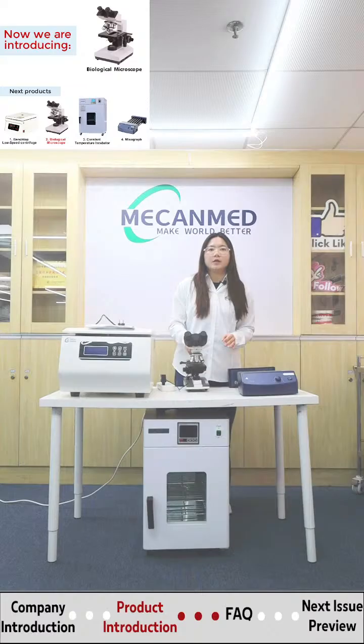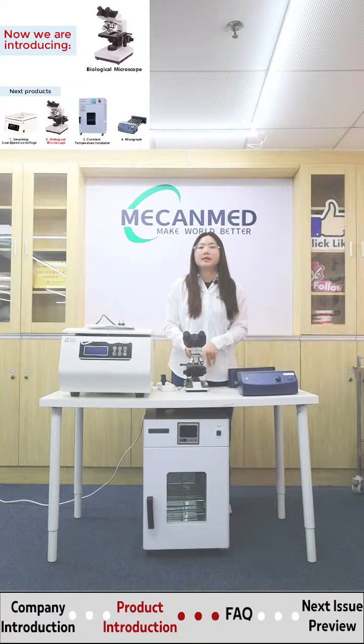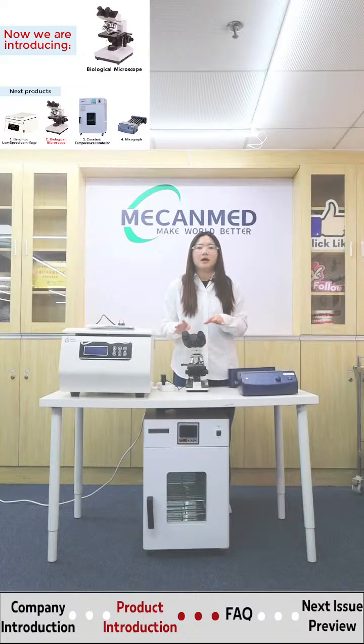Use the fine focus knob again until a clear image is obtained. Always locate and focus the specimen with the low power objective before switching to the high power objective. After the observation, lower the stage to its lowest position and then remove the specimen. Turn the illumination knob to the dimmest setting and then turn off the power.